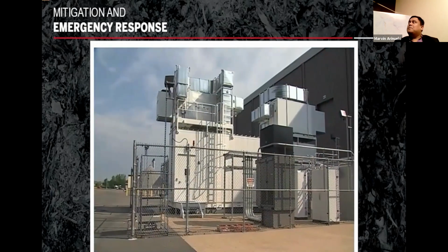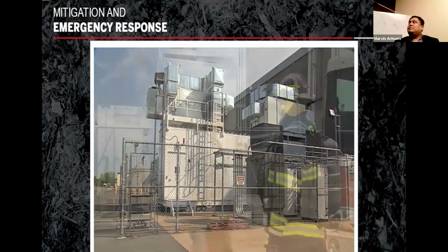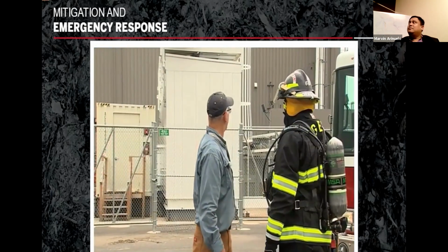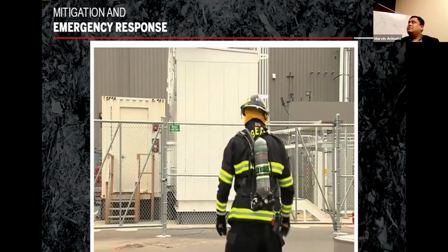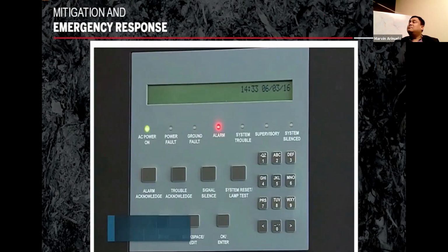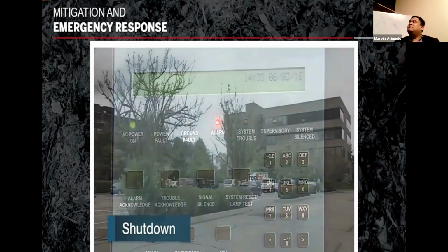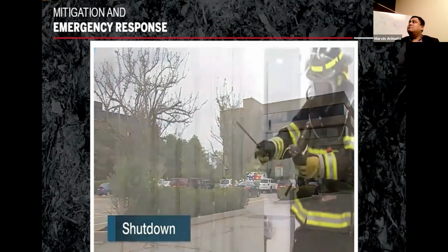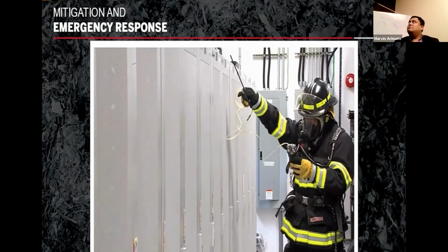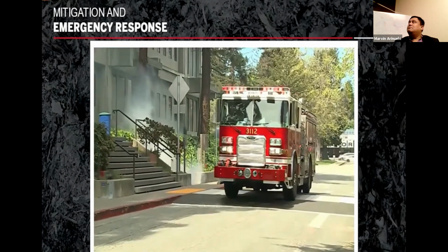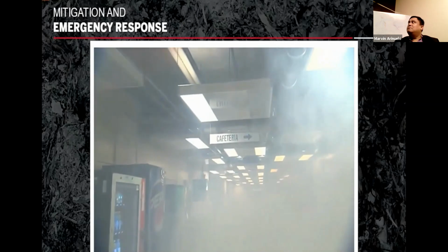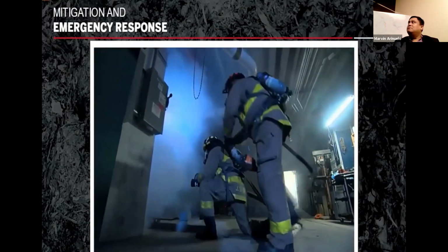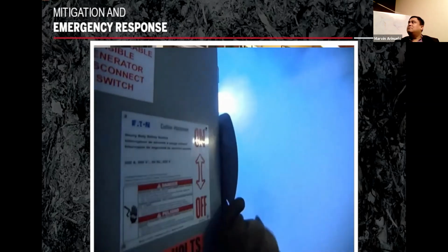After identifying the presence of a BESS, determine the level of power that must be shut down or secured in the structure based on the severity of the incident. For example, a fire alarm activation in a building with no smoke conditions present may not necessitate disabling the system. However, a response to a fire in a building that would normally require securing the power to the entire structure would also require the disabling of the BESS.